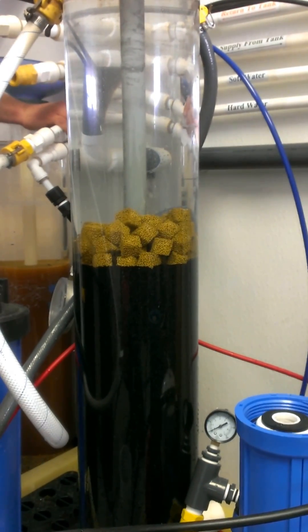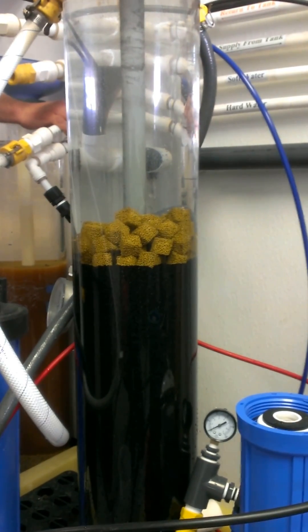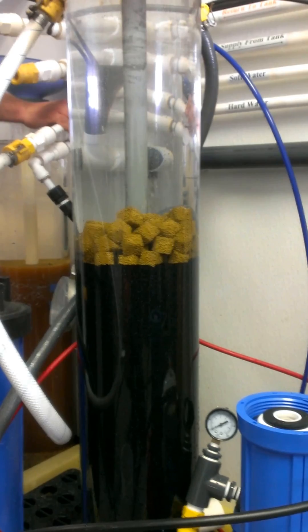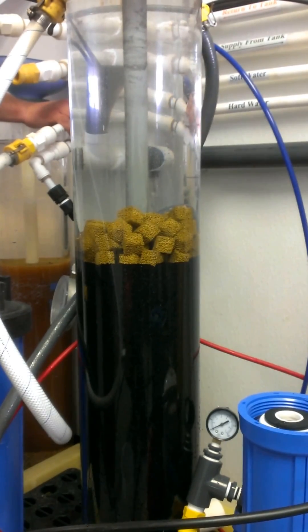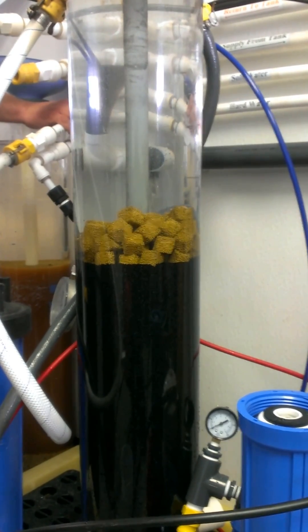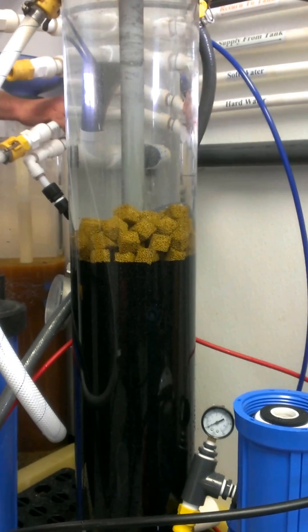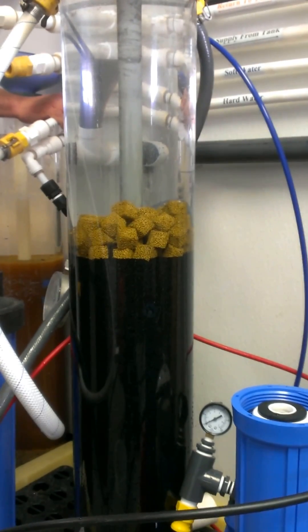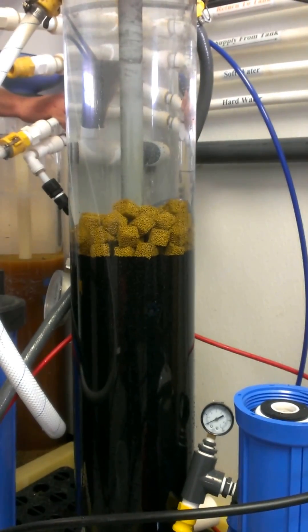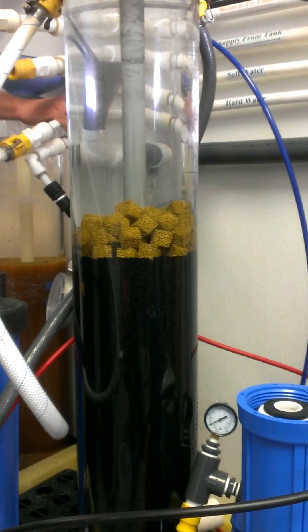Here I have about 0.6 cubic feet of carbon in an 8 by 40 vessel. It's actually 7.5 inch ID and I have 56 KDF cubes. So there's 56 cubic inches of KDF in here. And we're going to backwash this at about 3 GPM.